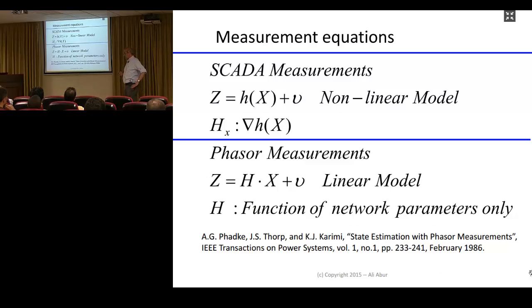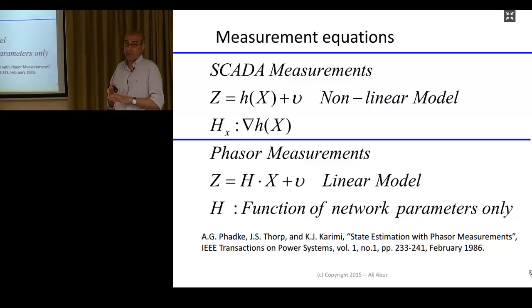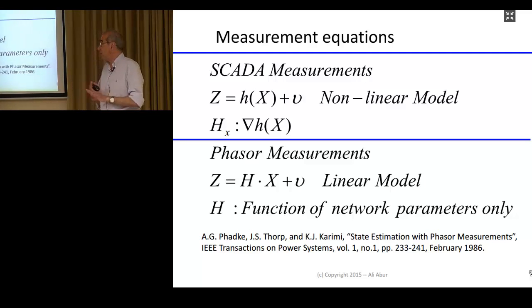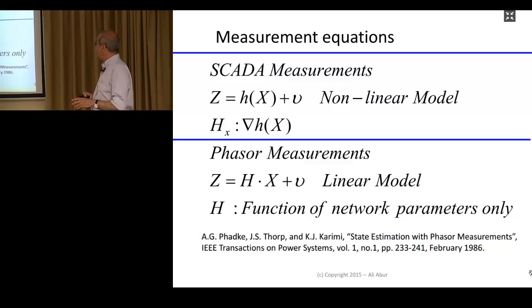Okay, so those are a brief overview of what we mean when we talk about phasor measurements, what we mean by phasor voltage measurement, phasor current measurement. So these measurements come in, and in the old days when we did not have PMU measurements, we strictly relied on SCADA. SCADA stands, as you know, for supervisory control and data acquisition. And essentially that set includes power flows, power injections, of course both real and reactive, and voltage magnitude and current magnitude measurements. So if you are using those measurements and you write out the equations for the measurements, they are nonlinear.